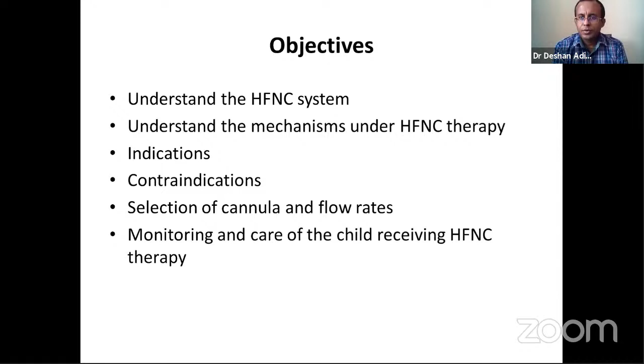The high flow system, as you can see, is composed of several parts. Here you have the machine, which has an air blender. Air is drawn in from the environment, and we also supply oxygen-rich gas through the machine, where it is blended and then brought through the humidifier. Sterile water is supplied to the humidifier, where the gas is mixed with the hot water vapor.